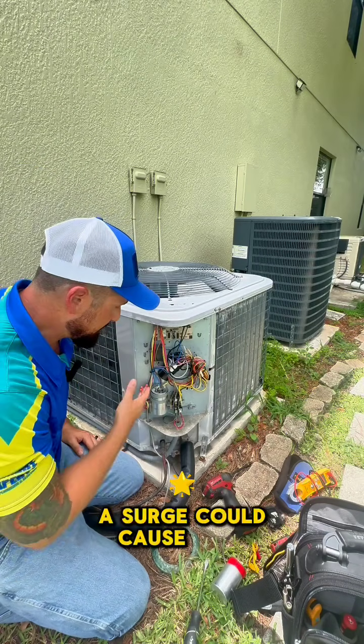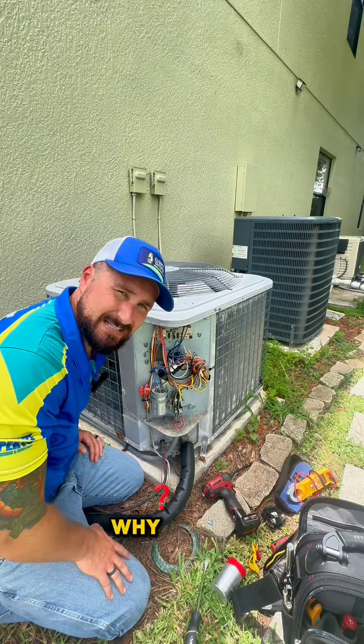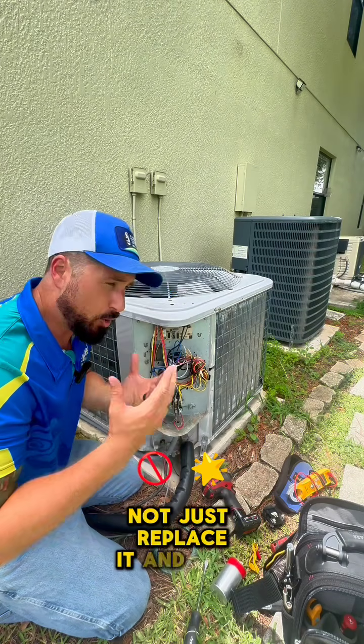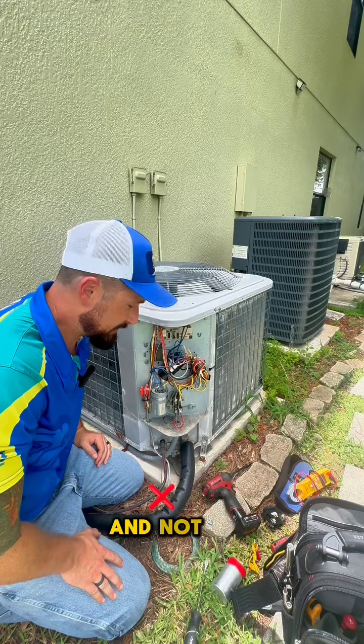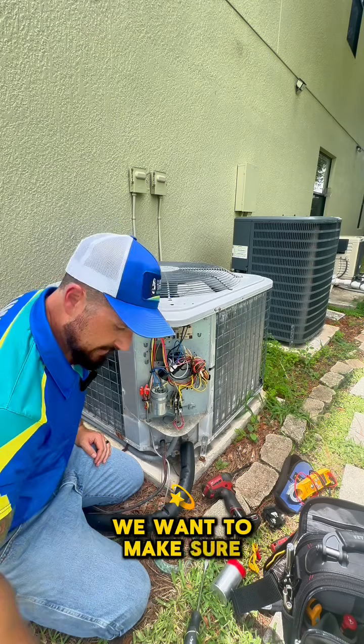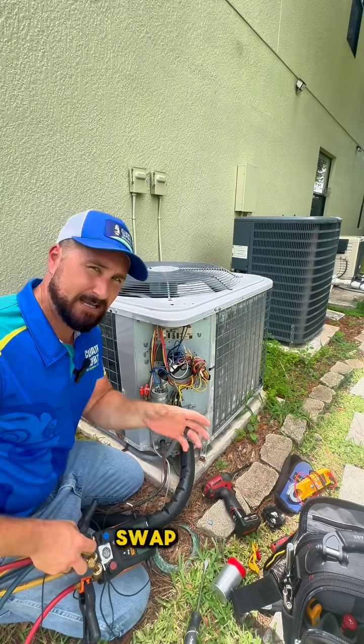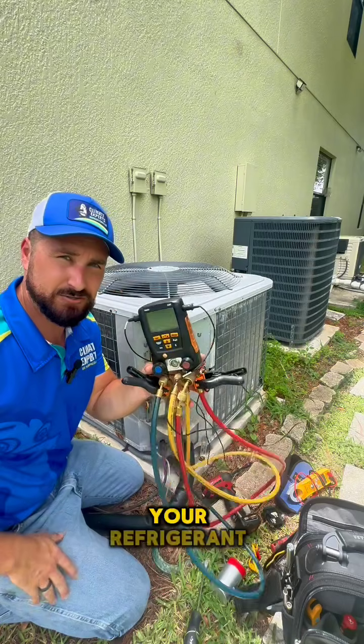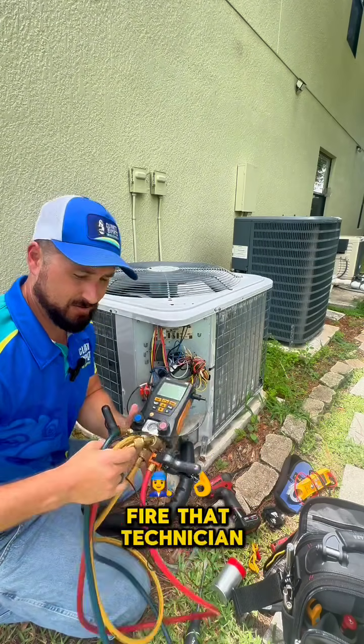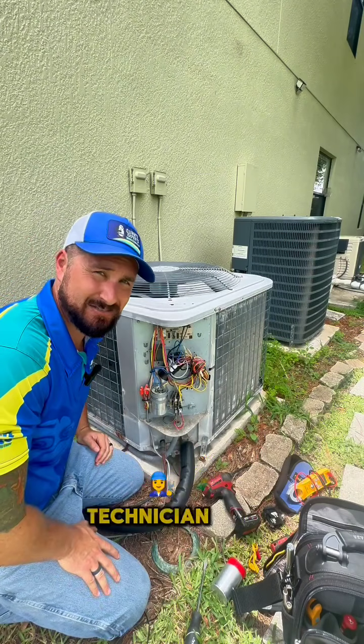A surge could cause this capacitor to fail. So we need to find out, why did this capacitor fail, not just replace it and hope that it's just going to magically work again and not fail again. So we're going to want to make sure, if you have a technician that comes out to your home and swaps that capacitor out and does not check your refrigerant pressures, fire that technician. Okay, that is not a good diagnostic technician. That is a part swapper.